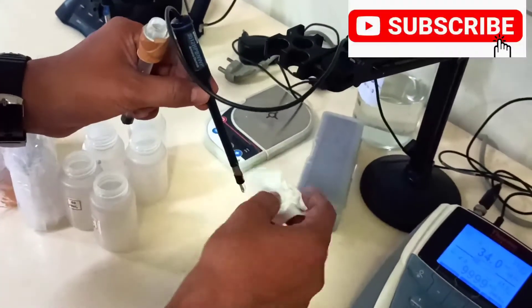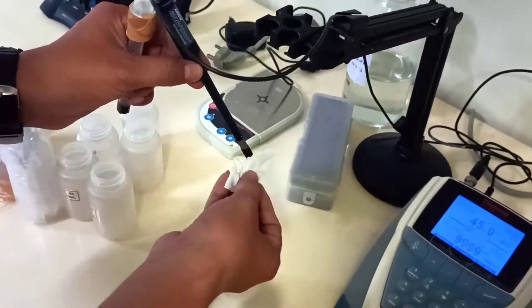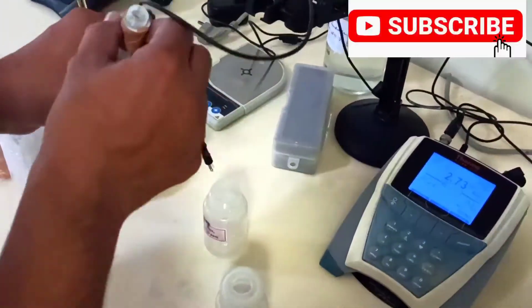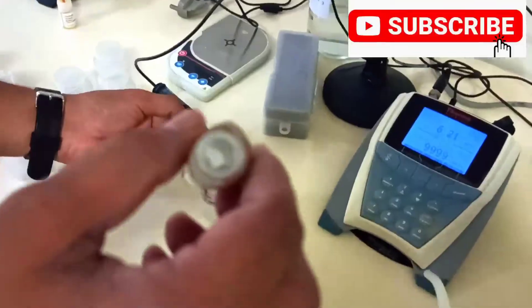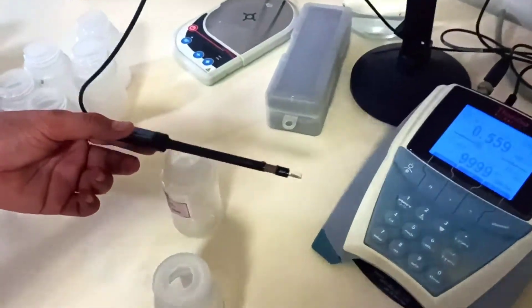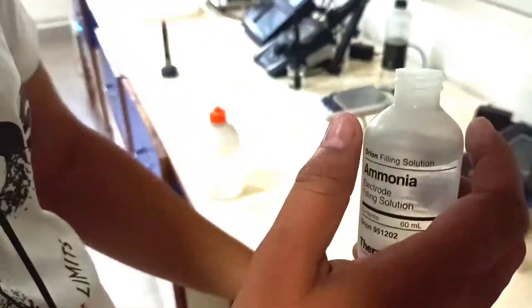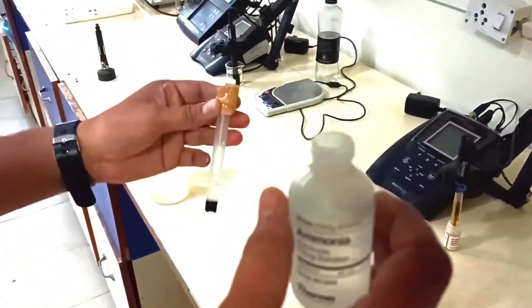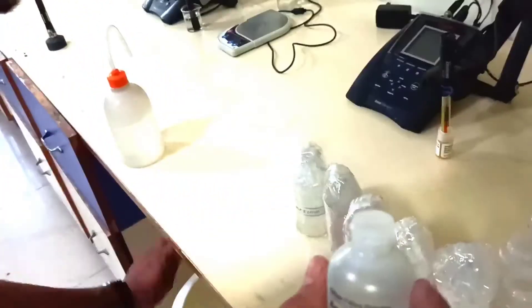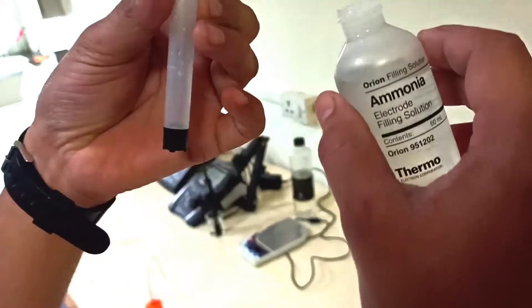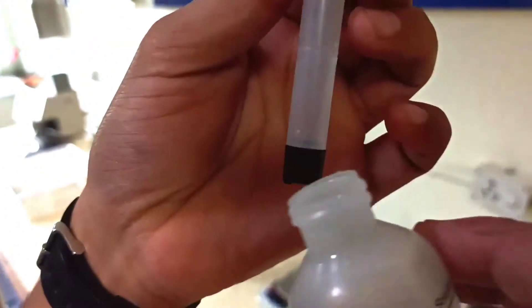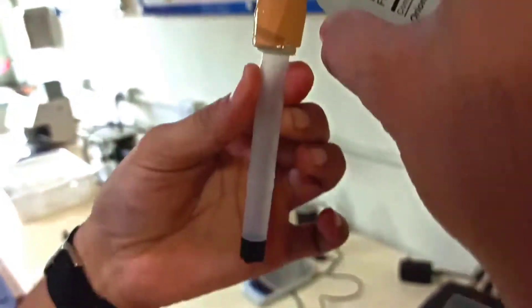For connecting with us, please subscribe our channel for getting more videos. With the help of tissue paper, we are drying this bulb very carefully. Now we are going to fill the electrolyte filling solution in the outermost case. First of all, we rinse with electrolyte filling solution, take very little, and fill up to the mark.